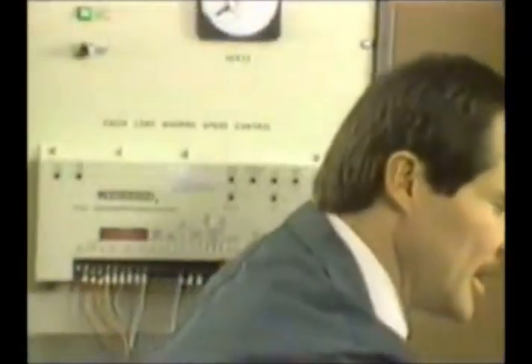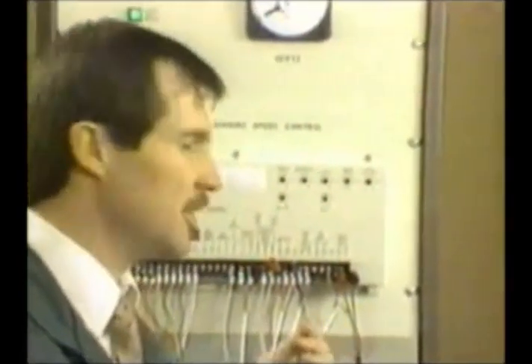And to show you that, I got a calculator here. The number of teeth on our gear is 156 teeth. So we're going to take 156 times, it's an 1800 RPM engine. Then I'm going to divide that by 60, and that gives us our 4,680 hertz. So that's how I figure out what the function generator should be feeding into the speed control.